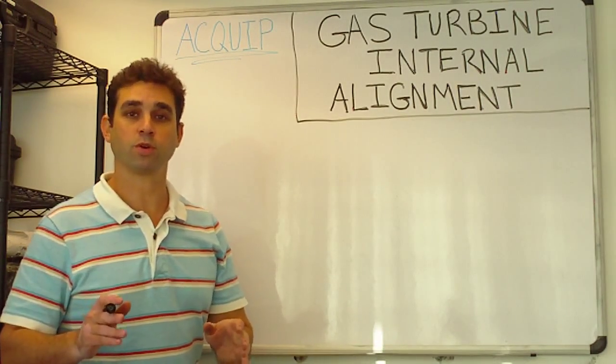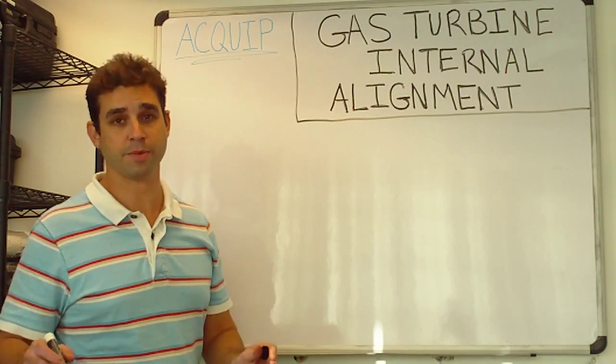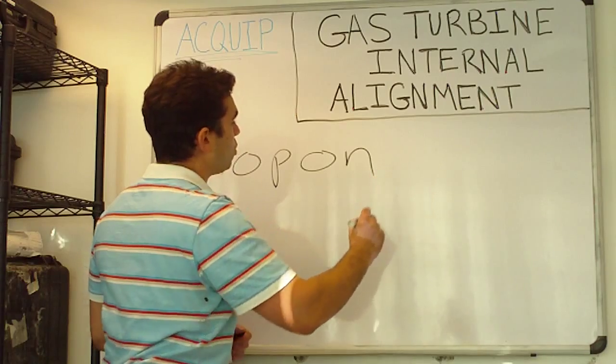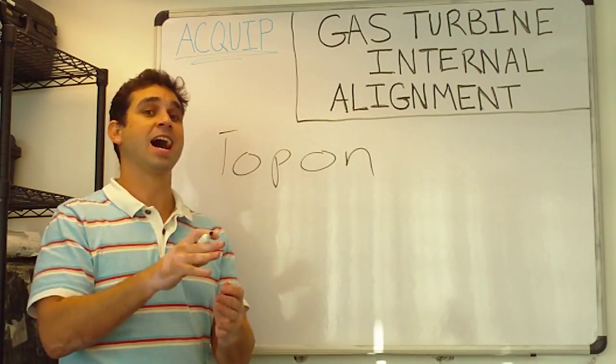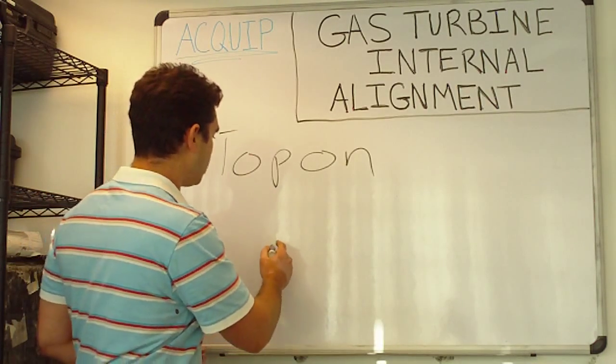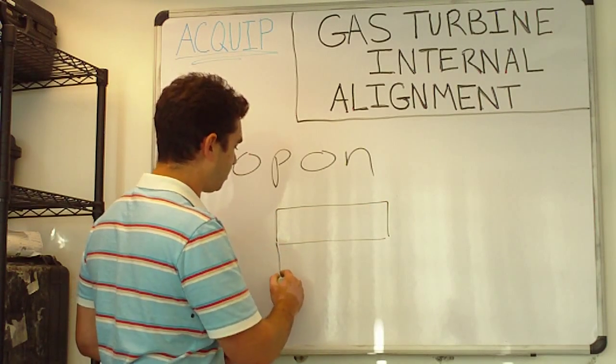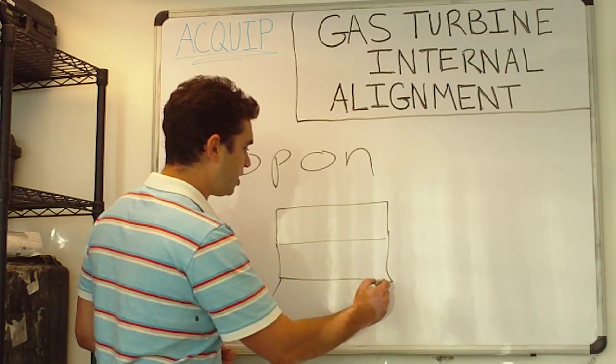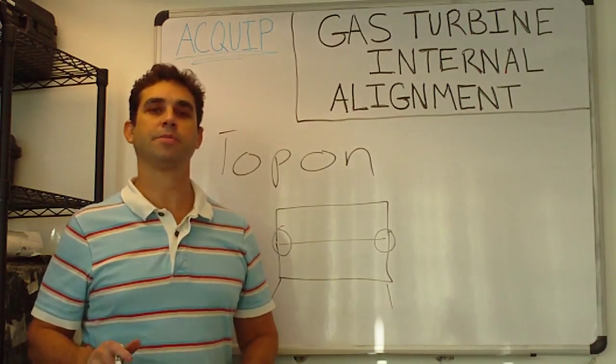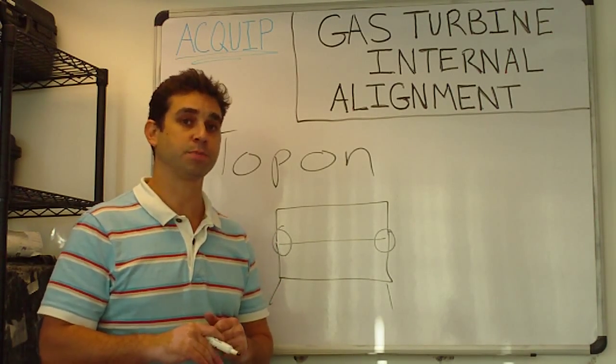The first thing that you have to remember when you do the gas turbine internal alignment is that you can only take the alignment readings with the top on. This is because in a gas turbine the top is a lot of support for the turbine. So by putting the top on you're creating the structure to mimic the online running of the turbine. And when we take our internal alignment readings we want the bores to be as close to its online running position as possible.